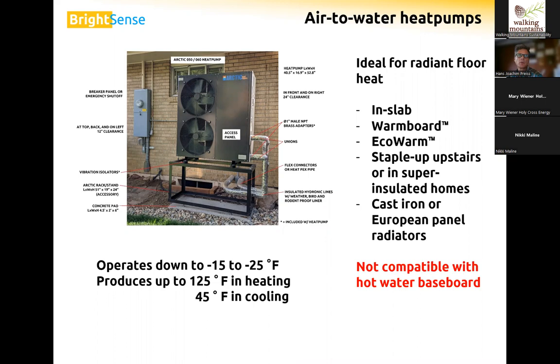Hot water baseboard is something that we cannot work with at this point. Hot water baseboard requires a high water temperature, 160, 180 degrees. That is because those are basically convectors, and convection requires higher water temperature. But for those people who have hot water baseboard, those were installed typically in the 80s and 90s, when construction quality was not really super well insulated. Homes were still up and coming at that point.